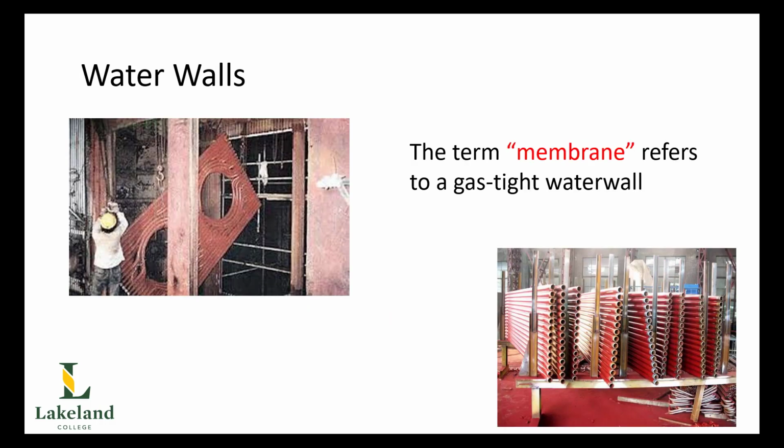So, in terms of the water wall idea, you can see here on the bottom right, there are photographs of water wall sections. And these will be installed in panels and then circumferentially welded into headers, top and bottom, as there'll be a header at the top and a header at the bottom that's going to connect these things together. You can also see the water walls can be made in different styles. The one pictured in the photograph top left there would be going around the burners, and you can see the tubes have been molded to go around them. Again, massively increasing our heat transfer surface area.